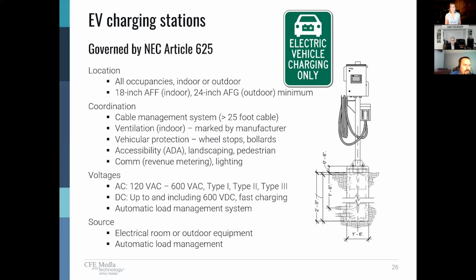And then I also wanted to touch on automatic load management systems, where you can utilize this, say, in an existing installation where you've got a limited capacity to add electric vehicle charging stations. You can utilize an automatic load management system to help balance capacity with the number of electric vehicle charging stations you have on site. And then code allows you to factor that in for feeder and for service size calculations as well.